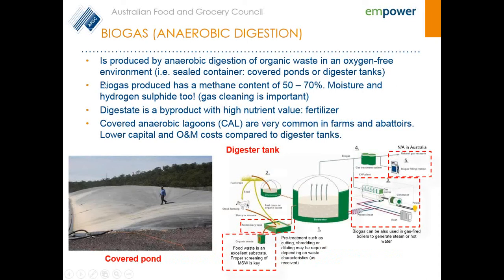Anaerobic digestion is the process where biogas can be generated from organic waste in an oxygen-free environment, which means you have to have a sealed container or a covered pond. The biogas produced normally has a methane content of around 50 to 70 percent depending on the process parameters and the composition of the waste. The remaining gas is mostly CO2, but moisture and sulfur content also need to be accounted for, as they can create a risk of corrosion. So cleaning of the gas is an important aspect.